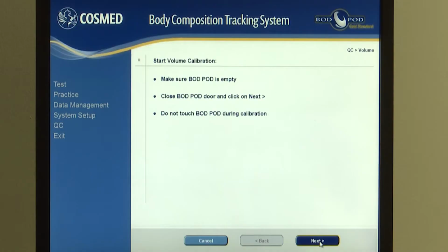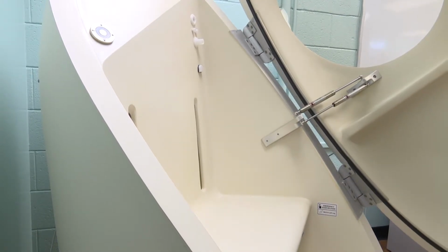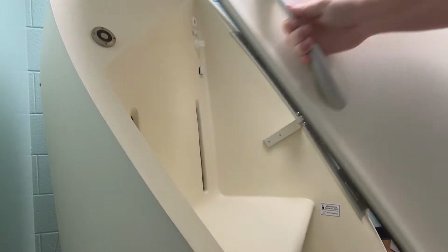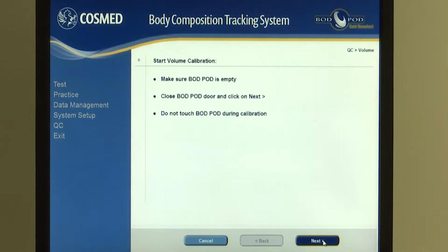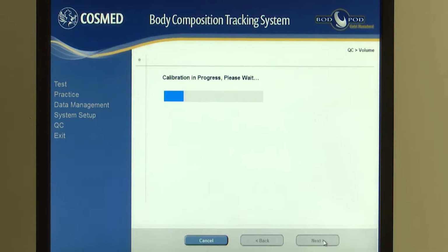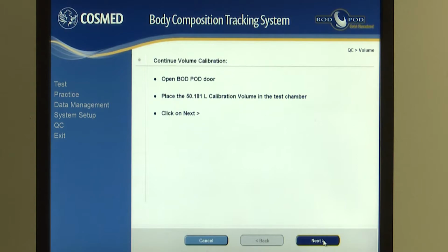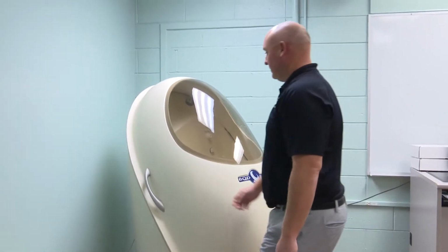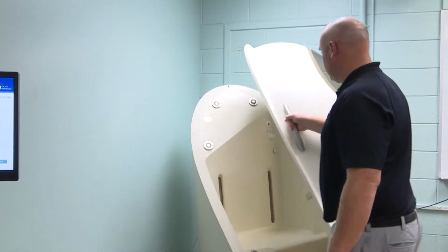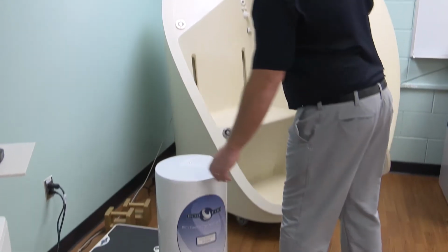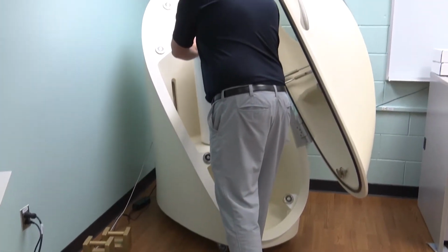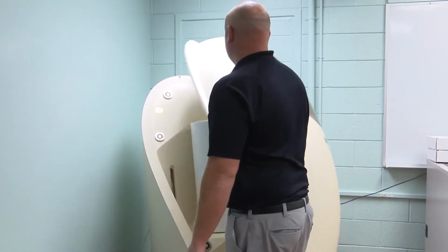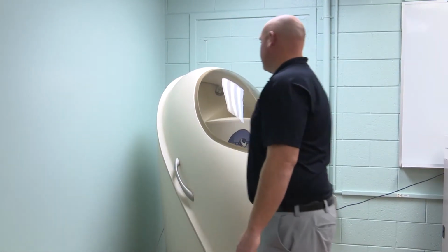The first measurement requires the Bod Pod to be empty. Each measurement takes approximately 45 seconds. The next 5 subsequent measurements will have the calibration tube in the Bod Pod chamber. The software requires the Bod Pod door to be opened and closed after each of these measurements.